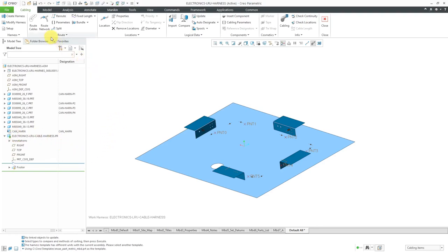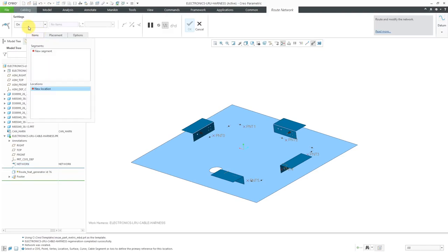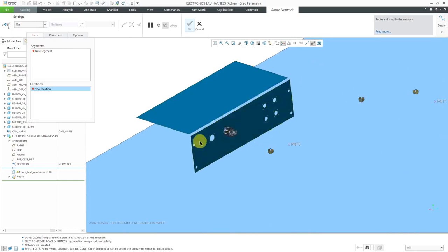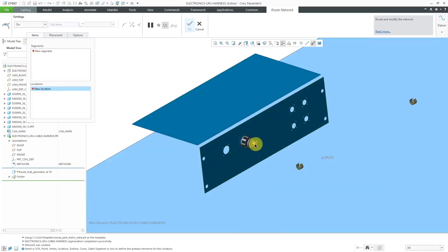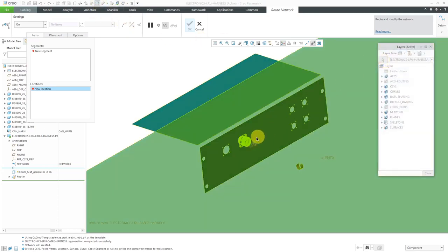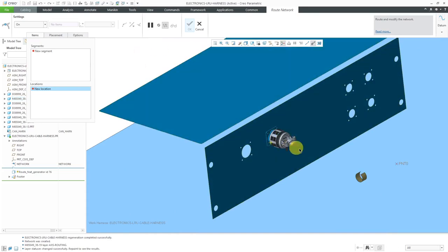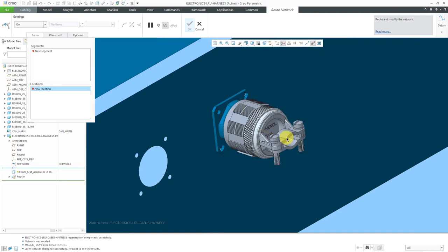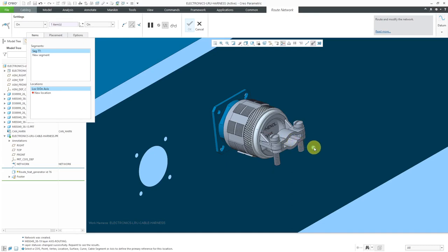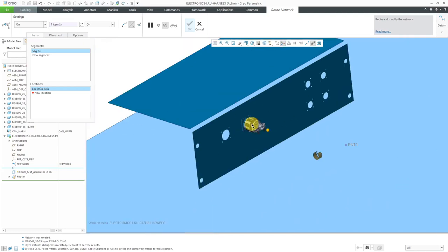To start out the network, you're going to use the route network command. By default it will be on some certain object. I want to start off coming out of this connector over here. Let me go to my layers — I'll use the pick icon to select the back shell and turn on the display of the axis for that part. There's the axis for routing. Then we can drag it off a little distance so that the wires will come out into that location.